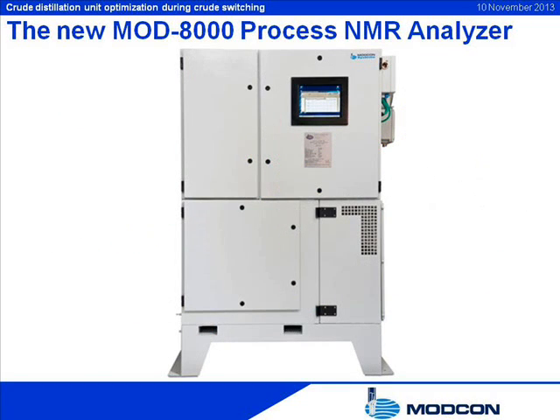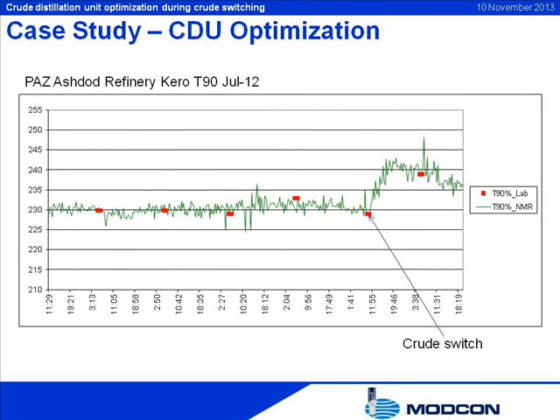The new MOD 8000 process NMR analyzer was successfully installed in two oil refineries, showing high accuracy and reliability. In both applications, this analyzer was used to quantify physical properties of crude distillation unit streams, including density, API, IBP, FBP, T10%, T90%, RVP, flashpoint, pourpoint, cloudpoint, freezepoint, and others. When crude switching occurred, MOD 8000 minimized the impact on CDU operation by an immediate adjustment to shift the exact cut point, so that the maximum production capacity of each product towards the most valuable distillates was achieved.